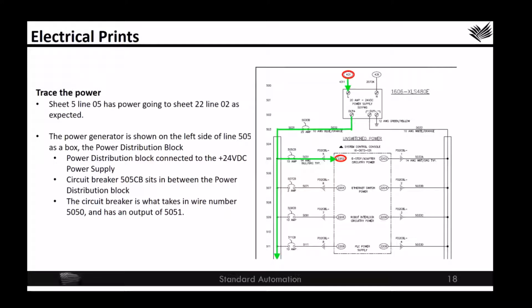If we're having problems with the power supply to the 24 volt power supply, then we could trace the power back all the way to the transformer, and we would start by looking at sheet 4, line 31. That supplies power to the 24 volt power supply. And eventually we would trace our way all the way back to the transformer, where the ultimate power supply is brought into the system.